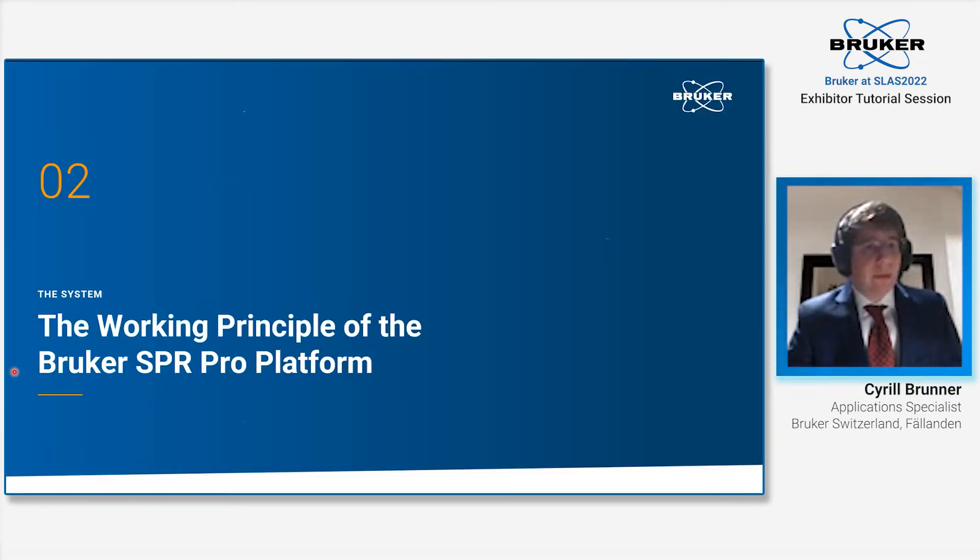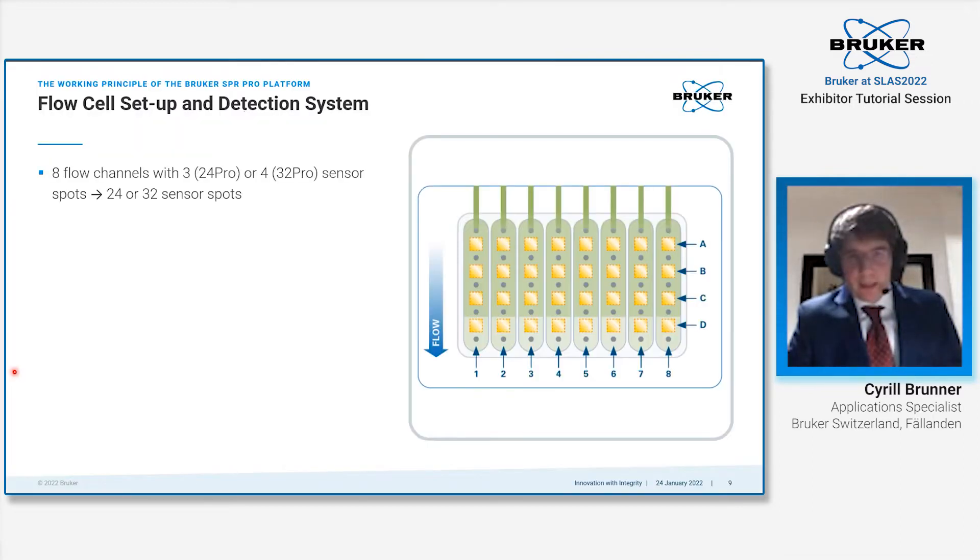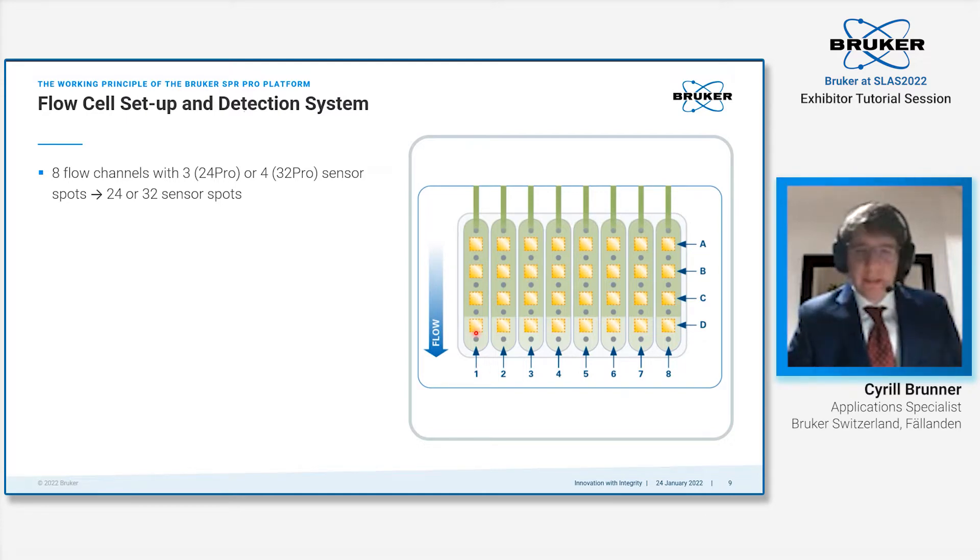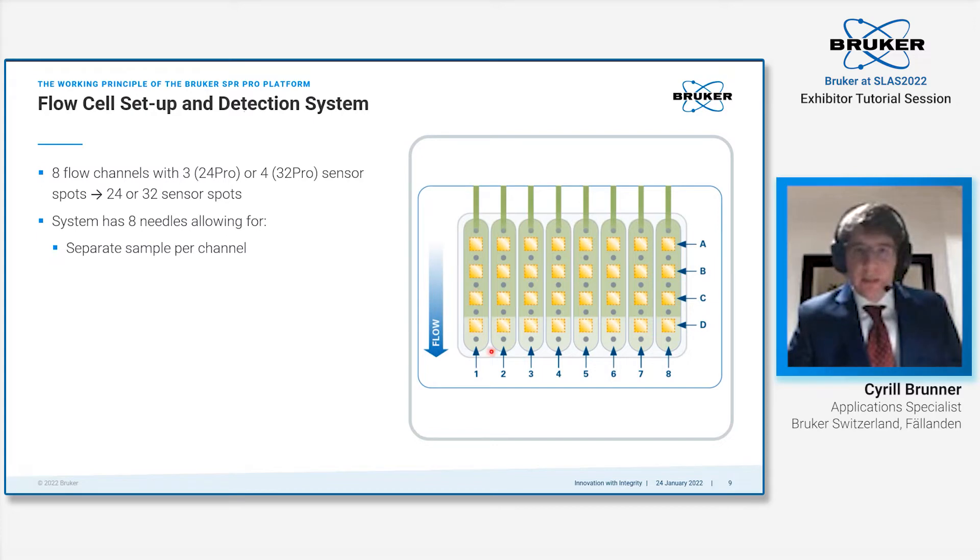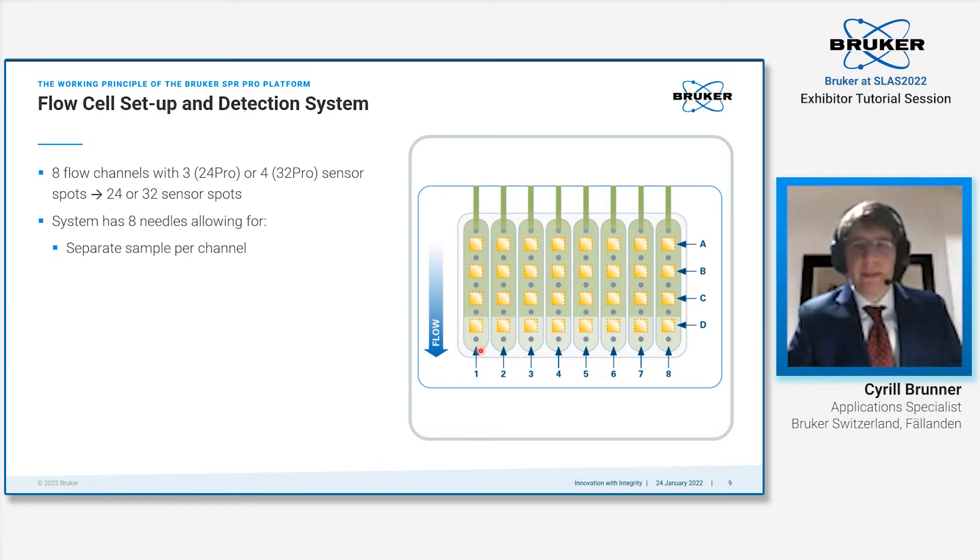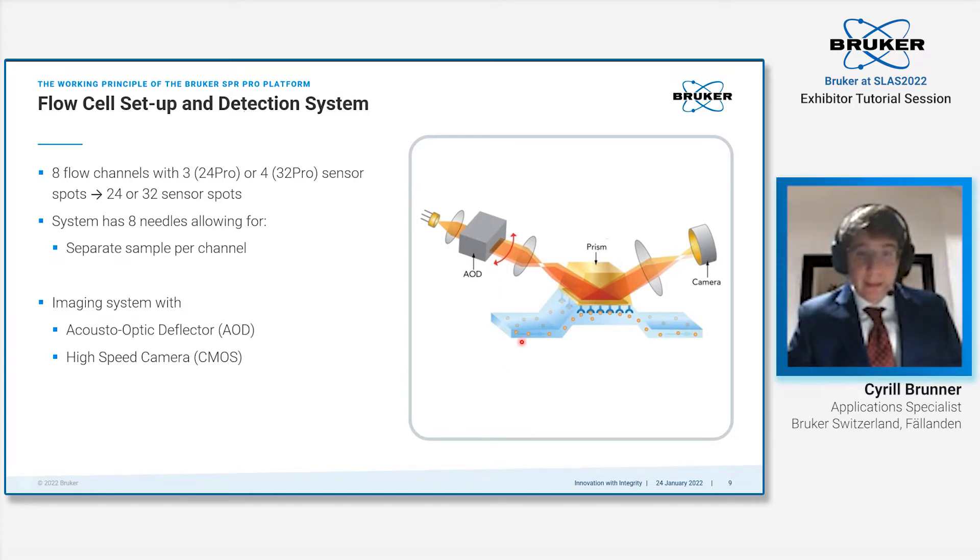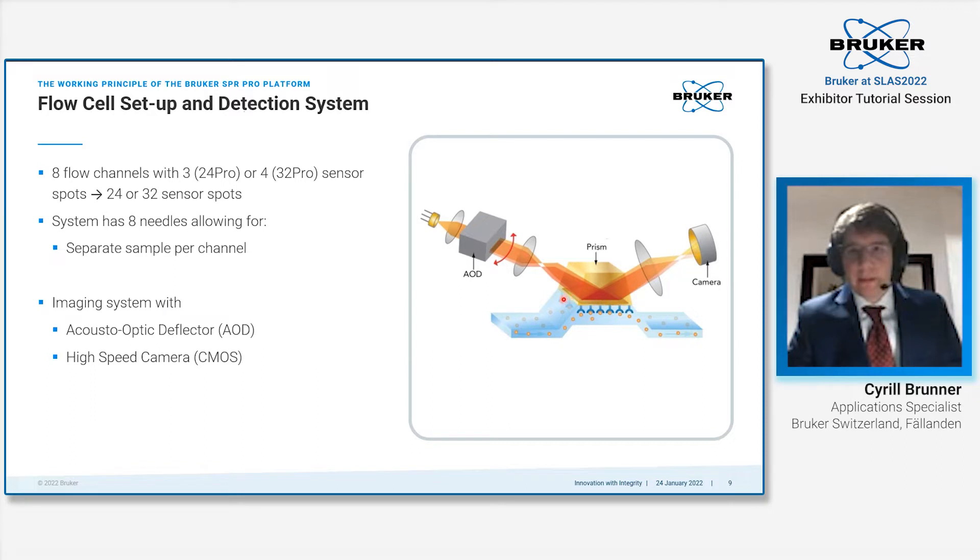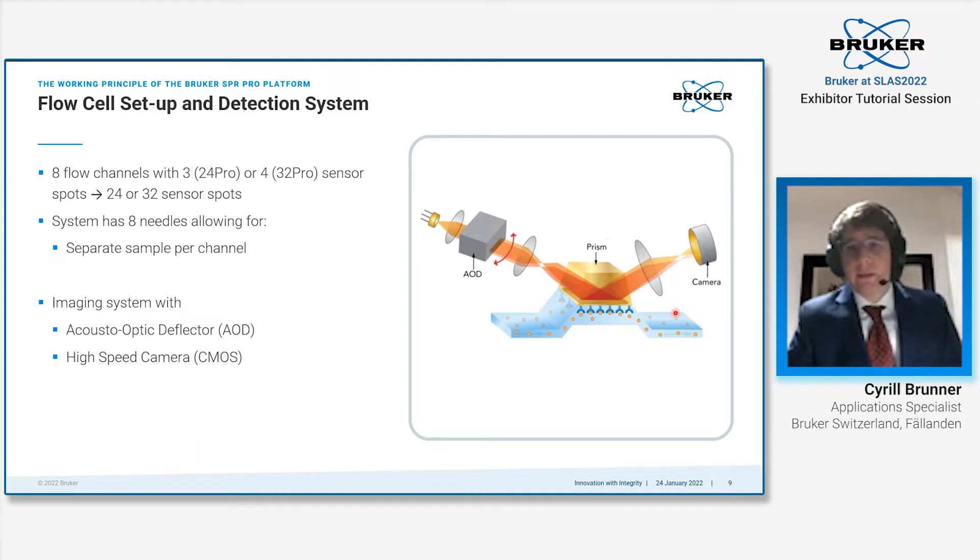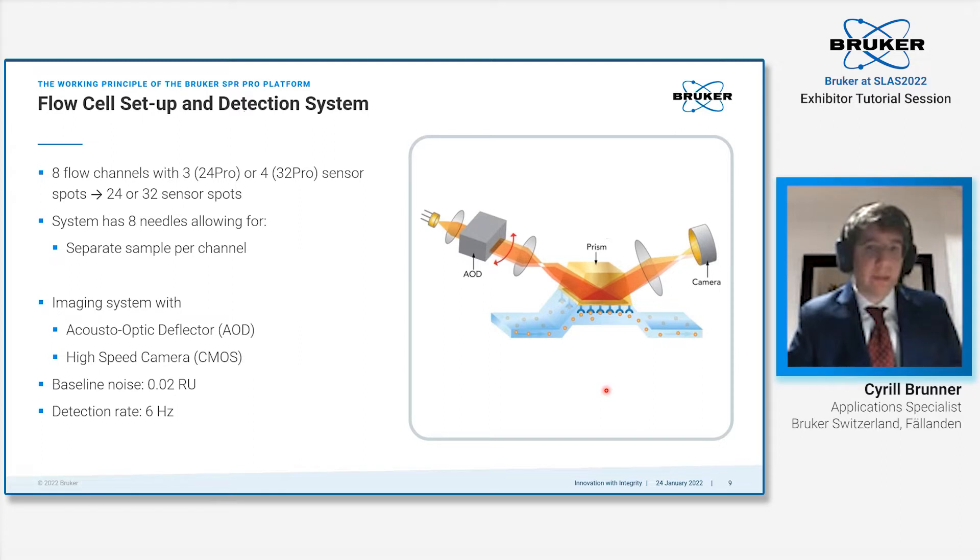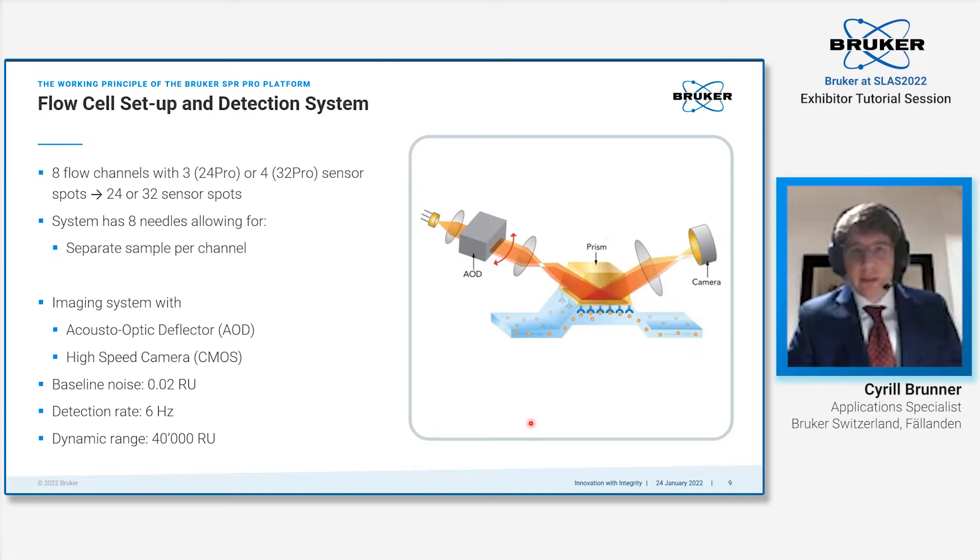Then we come to our new SPR Pro platform and how it actually works. The system is an eight-flow channel system with either three or four sensor spot rows, giving it overall 24 or 32 sensor spots. Each flow channel is individually addressed by a needle, so you have eight different samples that you can test simultaneously. It's an SPR imaging system using an acousto-optic deflector coupled to a bright light source and a high-speed camera. This allows us to be highly precise with a baseline noise of 0.02 RU and have a high detection rate of 6 Hz. The whole setup has a dynamic range of 40,000 RU.